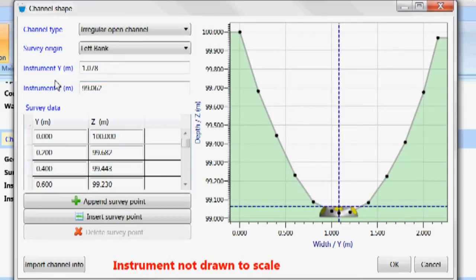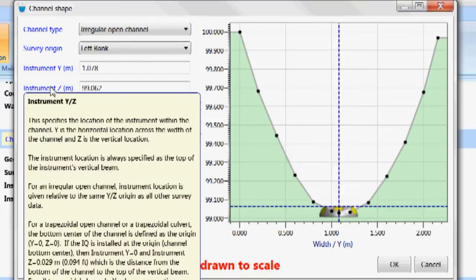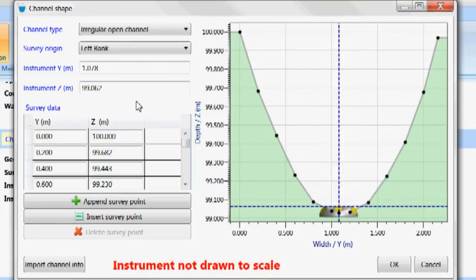The location of... One thing it's important for us to actually tell the instrument where it is within the cross section. In this case, we installed the instrument and then we performed a channel survey where we measured the actual cross sectional area of the channel. We actually measured the instrument's location in that channel in terms of its position, its width across the channel, and its actual elevation in the channel. So we put the width here, which is Y, which corresponds to this value here, Y. And we put instrument Z, which is the height of the instrument relative to the channel cross section.